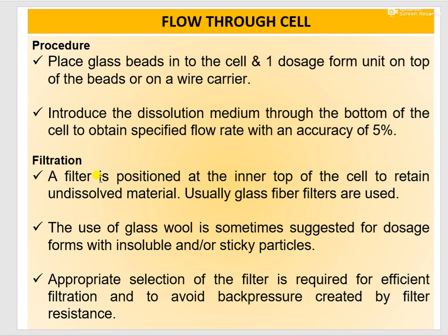Now how is filtration carried out? Filtration means once the tablet is dissolved and the dissolution medium is collected for analysis, at that time inbuilt filtration will be done. So how is it done? A filter is positioned at the inner top of the cell to retain undissolved material. So as we do filtration, here there will be an inbuilt filter at the inner top of the cell for filtration of undissolved material.